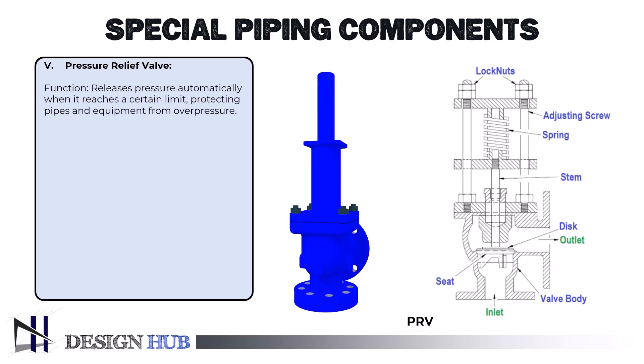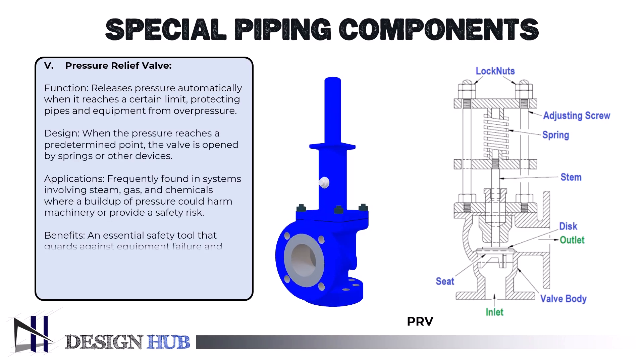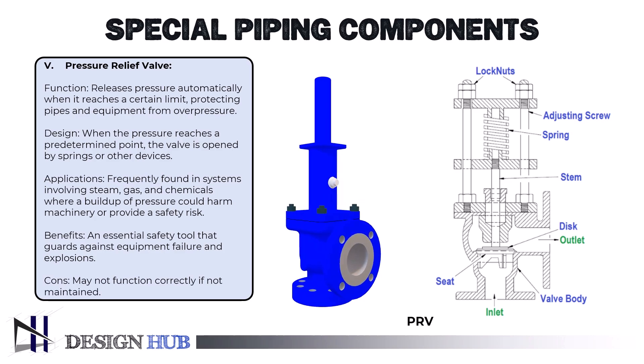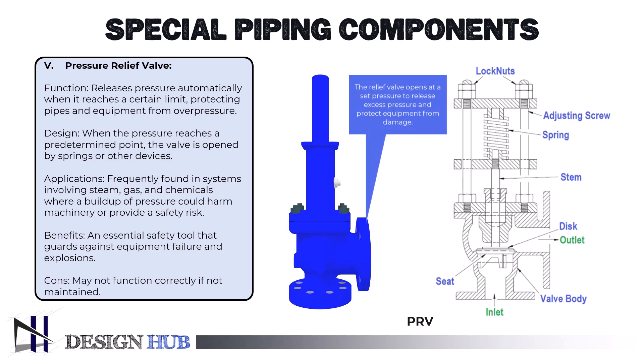The next one is a safety valve known as a relief valve, also called a pressure relief valve, PRV, which is used to regulate or limit the pressure within a system. If left unchecked, excessive pressure could build up and result in process disruptions, equipment or instrument failure, explosions, or fires. By enabling the pressurized fluid to exit through an auxiliary path, excess pressure is released. The relief valve is made or programmed to open at a specific set pressure to prevent pressures over design limits from damaging pressure vessels and other equipment.